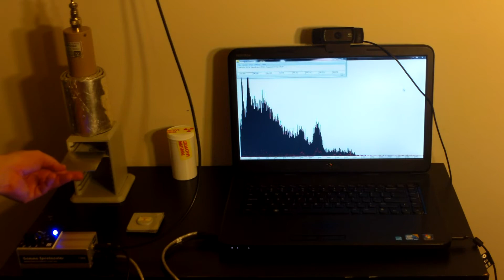This is rolls of lead, aluminum wrapped, and nestled around the detector itself. The reason is that it blocks out some of the background for a cleaner spectrum. And then this is a sheet of aluminum that I use to try to cut down those beta particles. I put that over top of the sample, in between the sample and here, because beta particles that hit the detector here will create various types of additional interference, such as X-ray fluorescence.